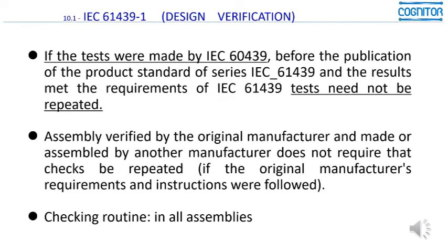Another point to call attention to is that if the tests were made by the previous IEC 60439, the type tests, and the manufacturer is now thinking about the new standard IEC 61439, these tests do not need to be repeated if the equipment was fully approved in the previous standard.